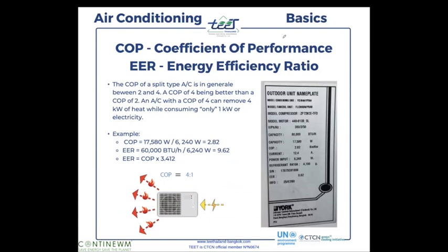Okay, so this is an example of a photo that we took during our visit. So this system was a York air conditioning. Okay, here we see York is the brand. Okay, we have a lot of reference, compressor type, the electrical motor, okay, the cooling capacity, okay, and we have the capacity in watt and in BTU per hour, okay. So these numbers are exactly the same thing. They are just expressed in different units.